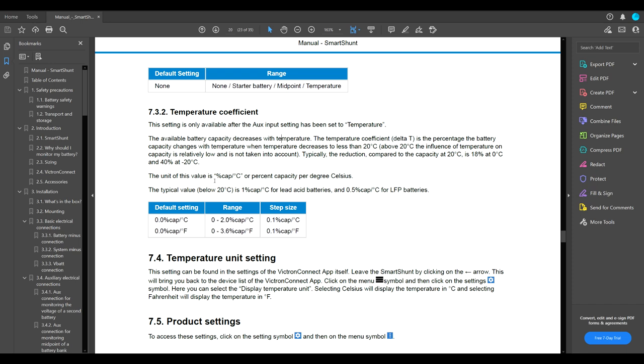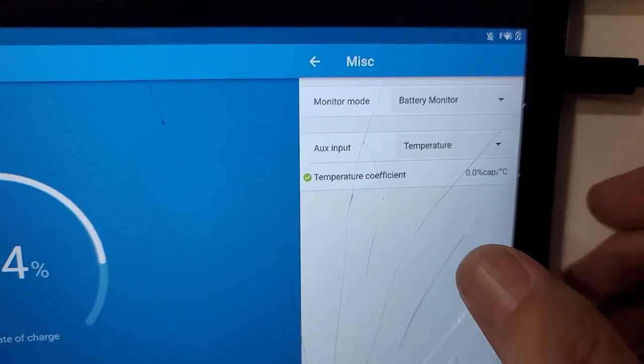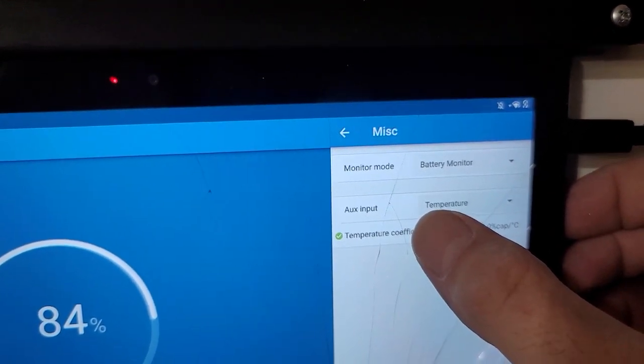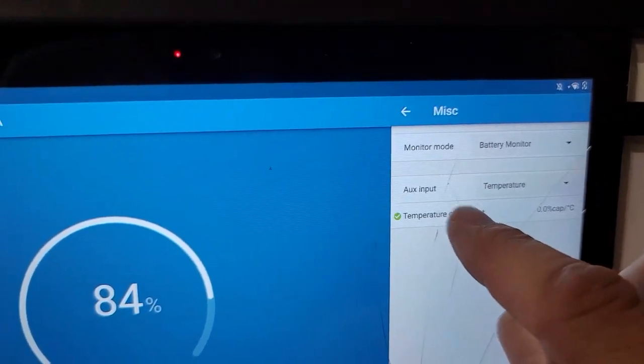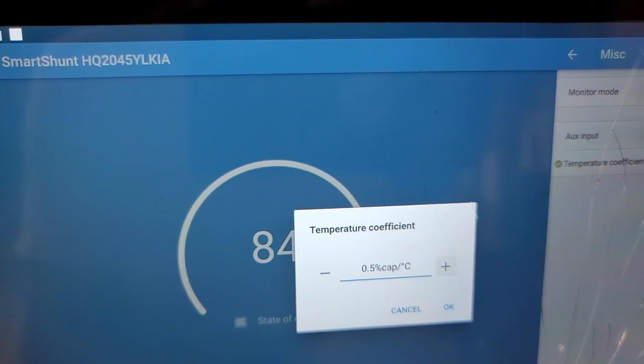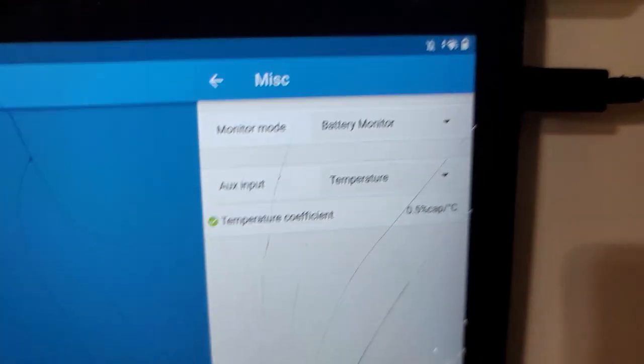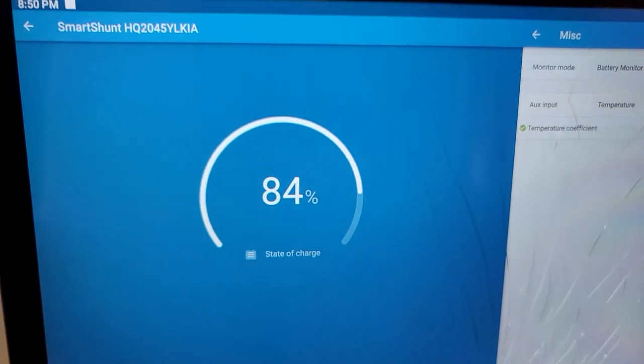The unit of this value, as I said before, is percent capacity per degree Celsius. Once again, we are going to keep this at 0.5% capacity per degree Celsius. As discussed in the instruction manual, we are going to set this temperature coefficient at 0.5% capacity per degree Celsius. We'll see what kind of a long term effect this has on guesstimating what kind of a capacity we have in the battery, in the power walls.